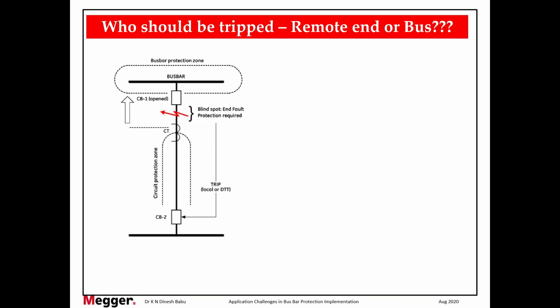Second point. Now let's club these two together. If a fault occurs here, bus bar will trip this breaker. After tripping the breaker, the fault is still fed from the remote end. And distance protection cannot sense this, because some relays even disable protection when the breaker is open. So when the breaker is open, what should I do? Same concept which we discussed earlier: when the breaker is open, this CT current is monitored. If current is present, bus bar will send tripping to the remote end. This is called end fault. So here we are tripping the remote end.